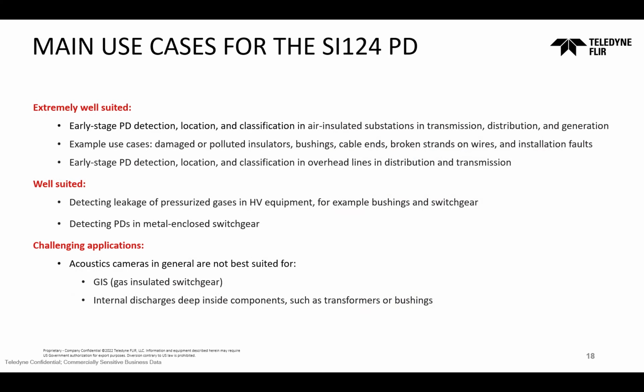Use cases include damaged or polluted insulators, bushings, cable ends. For example, if there's a PD in a cable end, cable termination, or a broken strand, you'll realize the camera gives a high criticality rating in many of those cases because they are sensitive. But the most valuable feature of the camera is not exactly the location of the partial discharge, because professionals working in a substation usually know more or less where the PDs are, they know their facilities and can even hear them sometimes. The real value is the criticality assessment, the classification of the partial discharge, and the recommendations we give in the cloud. That's why Dimitri mentioned the cloud is very important and very nice to use.